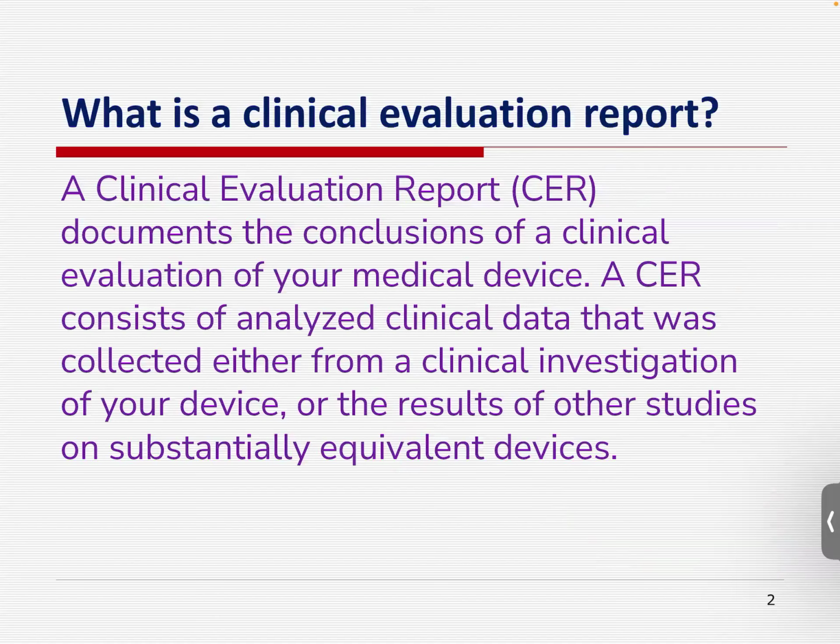So what is a clinical evaluation report? I will be focusing on the basics a lot so that the fundamentals are clear. It's a document that concludes the clinical evaluation of your medical device. Your pacemaker, maybe some device to measure BP, maybe a heart rate device, maybe anything, even artificial knees, all that.